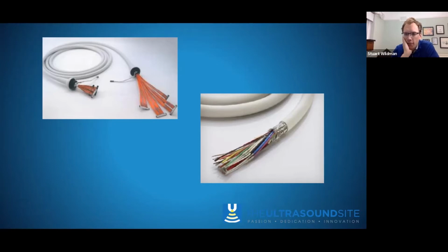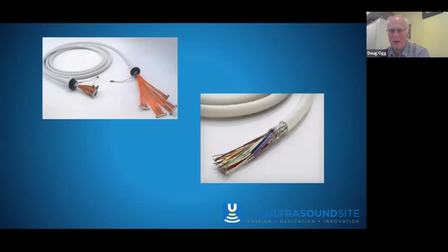And how easy is it to replace probes, Doug? Is it like changing a plug on a lamp? Far from it. Each wire in the cable has to be connected to the transducer element in the array, and it's not an automatic task. It's highly manual, and it's very often an extremely skilled task to do properly. That sounds expensive, Doug, the way you're saying that. Oh, it is. High frequency probes in particular have quite high rates of failure in manufacture. And that's one of the reasons why high frequency probes tend to be more expensive than lower frequency probes.